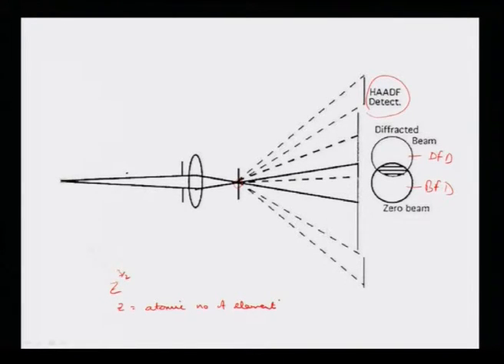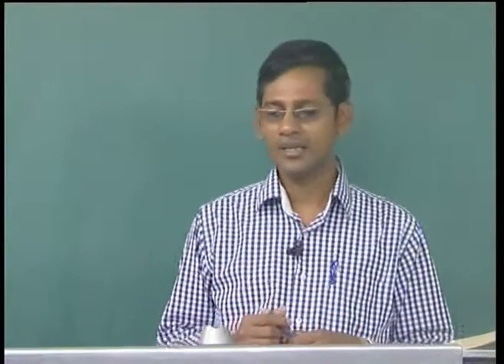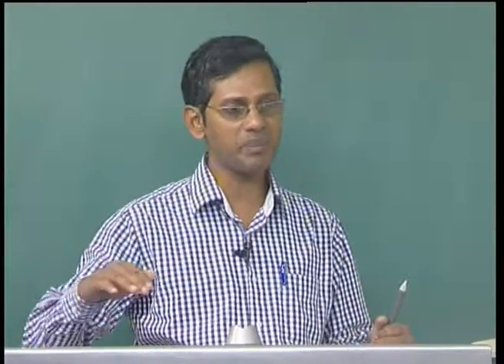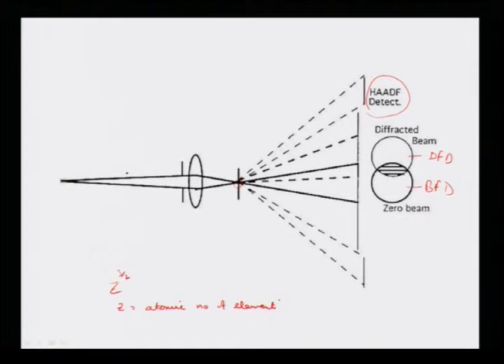Therefore, these HAADF detectors, by collecting and displaying the signal, tell us about the chemical composition of phases present in the specimen. The microscope described earlier has a HAADF detector that takes signals coming from the specimen at a slightly larger angle than the commonly diffracted beam in an annular detector configuration and displays them on the computer screen.